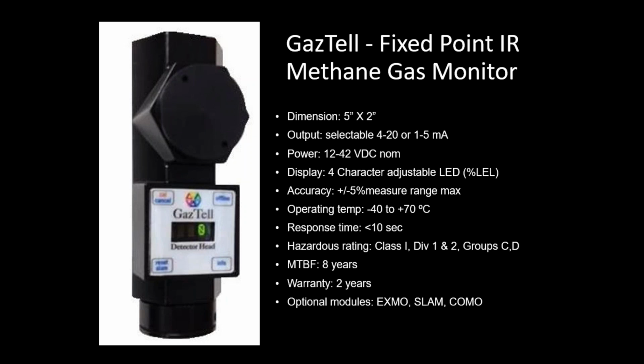And we've been able to achieve all three of these advantages with the GazTell by minimizing the footprint. It's a 5-inch by 2-inch, which is probably one of the smallest IRs that you're going to see out there. We've been able to reduce the power, using only about 77 milliamps per detector head for the fixed point IR. I believe the electrochem and the other types of IRs vary in power requirements. Electrochem are probably down near 40. Catalytic bead will be up near somewhere about 120 milliamps. But it's still lower power than most of our competition out there.